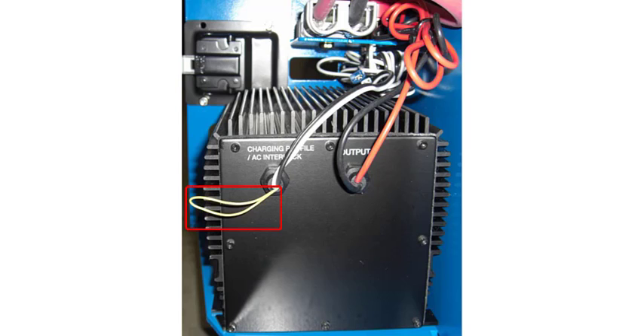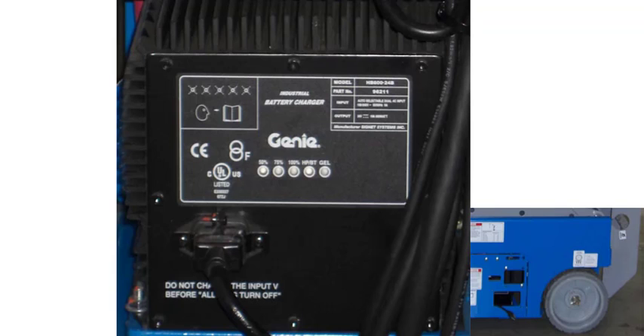The yellow jumper wire is closed for wet lead-acid batteries. Cut the jumper, and cover the bare wire ends, in applications where gel batteries are installed. The red and black wires are the output wires connected directly to the batteries. The faceplate on the charger has status LEDs, to display the state of charge throughout the charge cycle. They're also used to flash fault codes, along with an internal audible alarm.